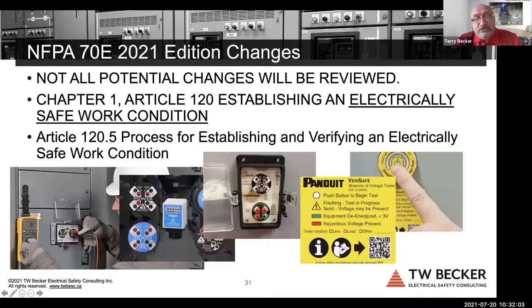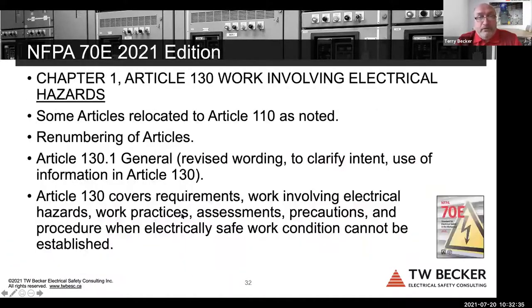So this language continues to evolve to further clarify in 70E that these automatic testers can be used. In Z462, we say that they're still an alternate, that they're not and cannot be used exclusively. So there's a technical change or a content change that's unique. 70E says you can use these independently of any test instrument, and in Z462, we did not and still do not have that language. All right, so watch these subtle language changes, words and terms and phrases that happen every 3 years, very typical, and a lot of global wording changes.